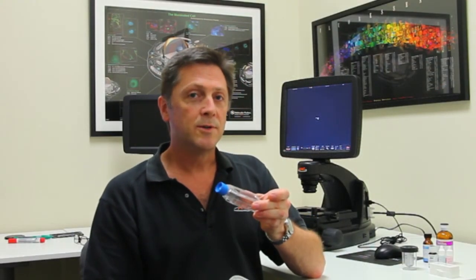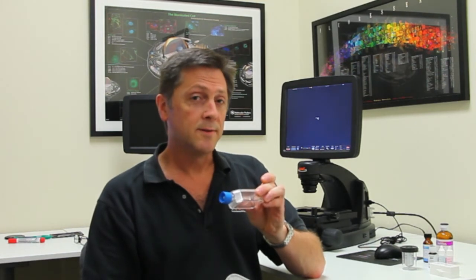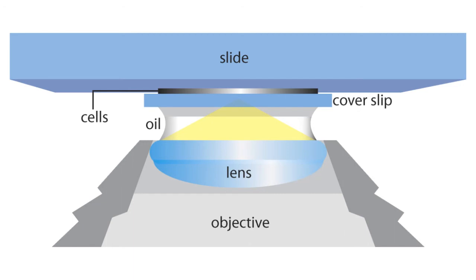These kinds of samples can be visualized using long working distance objectives, but an oil immersion objective requires your sample to be prepared with a glass cover slip. The oil goes between the objective and that cover slip, providing this optical link to give you maximum resolution and brightness.